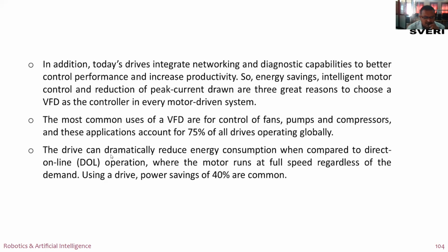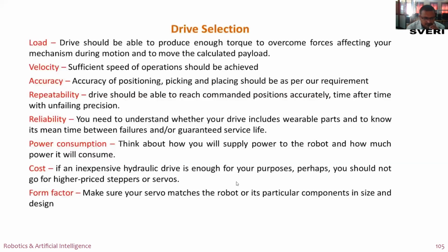The drive can dramatically reduce energy consumption when compared to direct-on-line operation, DOL operation, where the motor runs at full speed regardless of the demand. Using a drive, power savings of 40% are common. Therefore, these are the drive selection criteria. I will see this video after this slide.